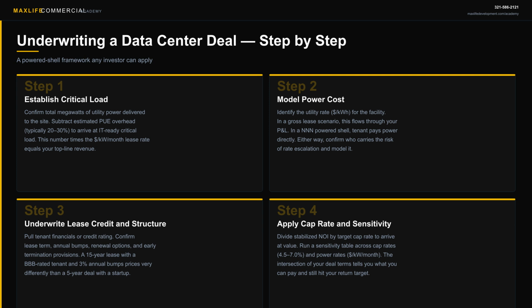Step 2 is modeling power cost. In a triple net powered shell, the tenant pays for power directly, so your P&L looks a lot like a NNN industrial deal. But in a colocation or gross lease structure, power cost is your largest operating expense, and you need to model both the current utility rate and a reasonable escalation assumption. A 3% annual rate increase on a 10 megawatt facility is a meaningful number over a 10-year hold.